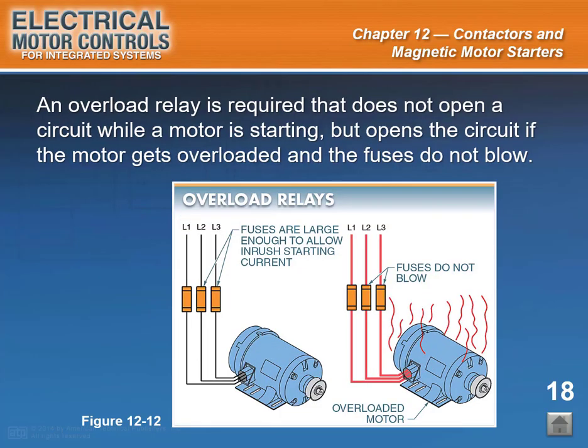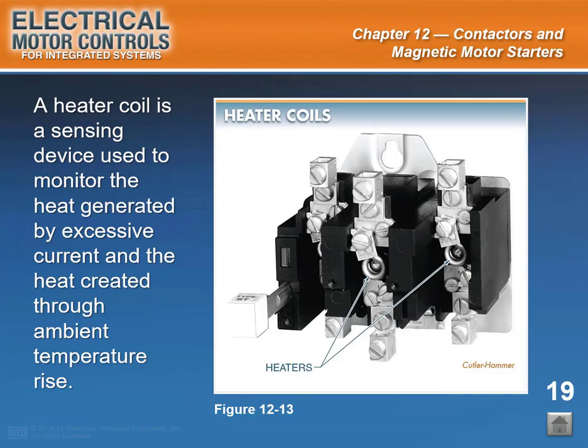Slide caption: an overload relay is required that does not open a circuit while a motor is starting but opens the circuit if the motor gets overloaded and the fuses do not blow. See Figure 12-12. Fuses or circuit breakers must protect the circuit against the very high current of a short circuit or a ground fault when the fuses do not blow open to protect the motor. End of slide 18. Start of slide 19.